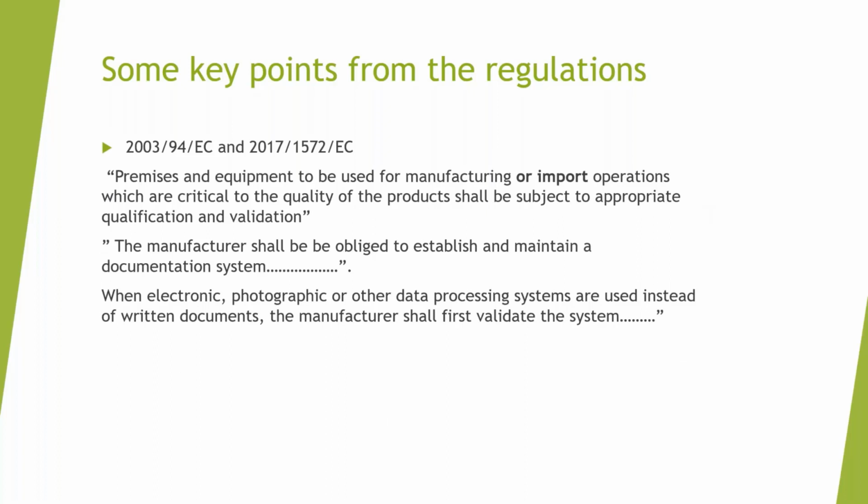So some key points coming out of Europe: premises and equipment to be used to manufacture or import medicinal products here that are critical to the quality of the product shall be subject to appropriate qualification and validation. So when we're talking about laboratory equipment, it often is electronic equipment made up of pieces of hardware and software, and those must be appropriately qualified or validated for use.